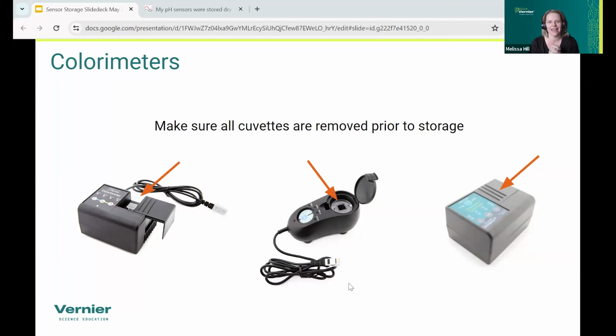The number one thing we see happening with these is that when people go to store them, they don't look inside and there was a cuvette in there, and then all the solution spills out of the cuvette into the colorimeter, and it's not all waterproof inside there. We've made some changes over the years to make it not as damaging, but especially if it spills out and it sits there all summer, that will ruin your colorimeter. So open those colorimeter lids and check for a cuvette. Take the cuvette out and store it without a cuvette in there.